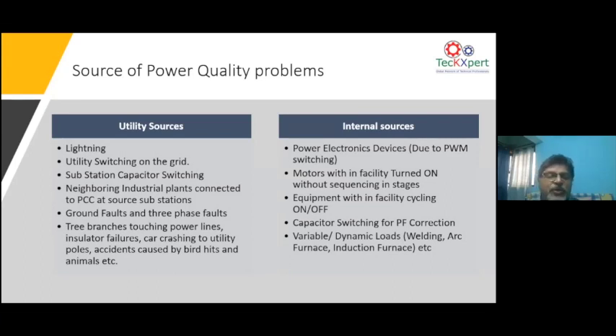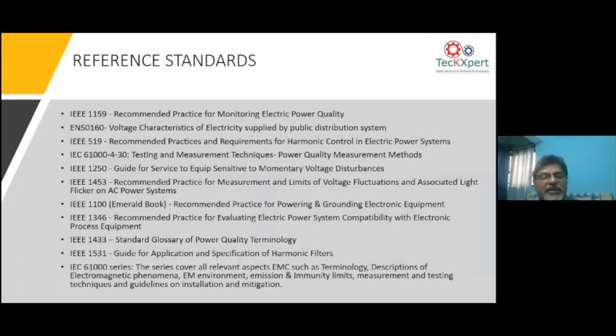Now, when it comes to maintaining voltage quality, when utilities use substation capacitor banks for switching, I have many customers who complained that their VFD or UPS has failed because of capacitor bank switching. The size of the capacitor bank in kVAr, the load at which you do the switching operation, and how many steps you have, all of that affects the switching related frequency on the grid. That is why consumers sometimes get affected by those switching surges, and their electronic cards fail.